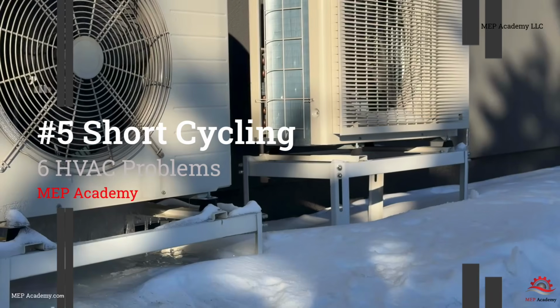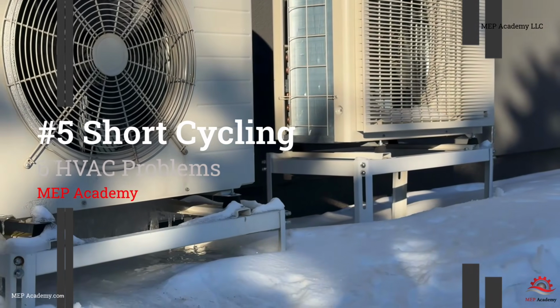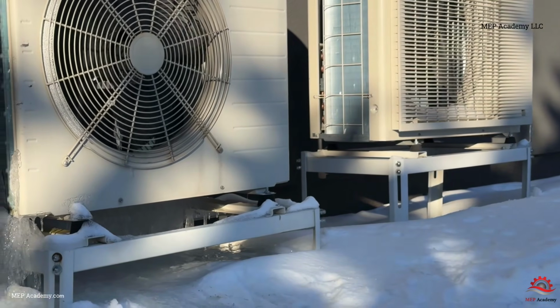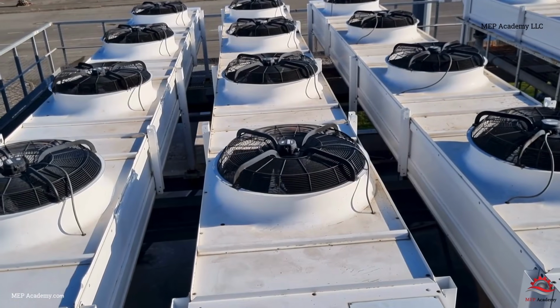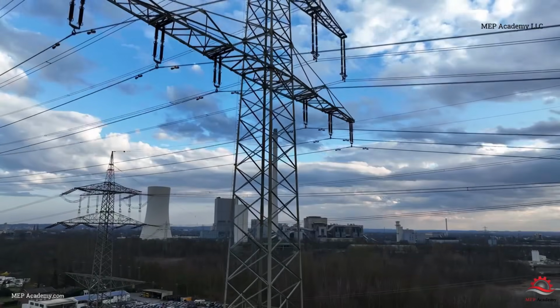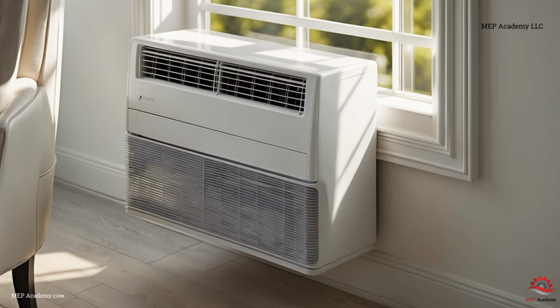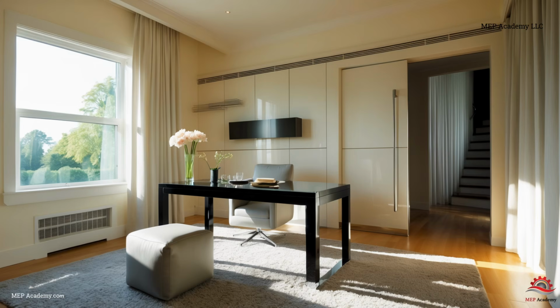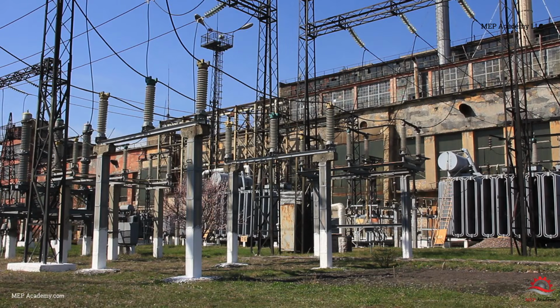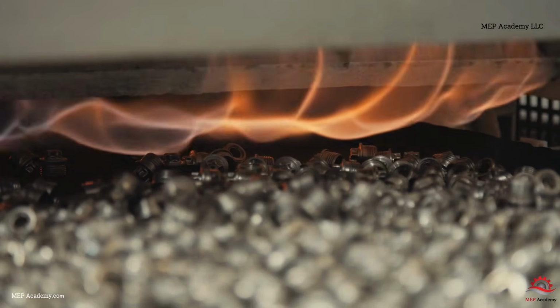Problem number 5, short cycling. A healthy HVAC system should operate in reasonably long cooling cycles. When a system starts and stops repeatedly throughout the day, efficiency suffers and equipment wear increases. This condition is known as short cycling. The compressor may start, run briefly, shut down, and restart again only a few minutes later. Each start places stress on electrical and mechanical components.